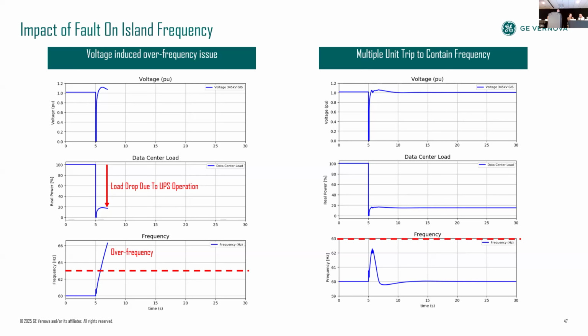And what this causes is the rate of change of frequency to rise very fast, to a point where it becomes uncontrollable. So all the generation units will trip when the frequency crosses a certain point, normally in the 5 to 6% range. So this UPS sensitivity to power quality events, which is also related to the non-fault ride-through characteristic of the load, is a problem from the plant design. One of the solutions, an operational solution to save the system from complete collapse, is to trip your generating assets on the plant side to stabilize the grid, so that you can start with a few units and not collapse the complete system.